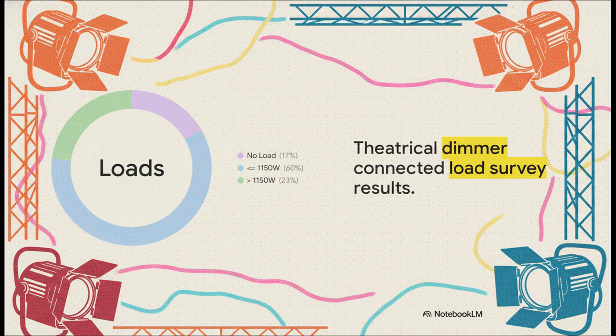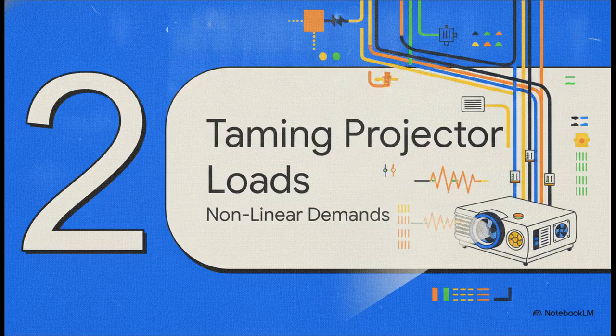If you look at survey data of theatrical dimmer loads, you'll see that 17% of dimmers historically had no load at all, and a whopping 60% were loaded to under half their capacity. Because traditional tungsten halogen lights have a low duty cycle, meaning they're turned off or dimmed down most of the time, the industry has had this built-in safety buffer that organically kept our actual usage well under that 50% diversity limit. Section 2. Taming projector loads, nonlinear demands.